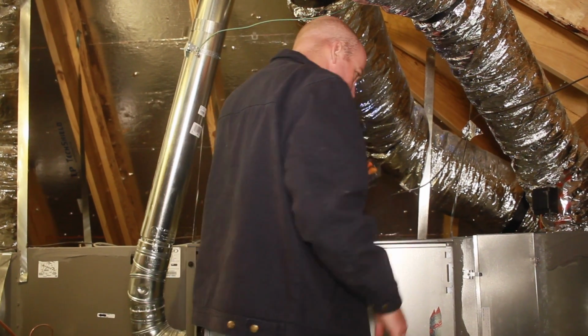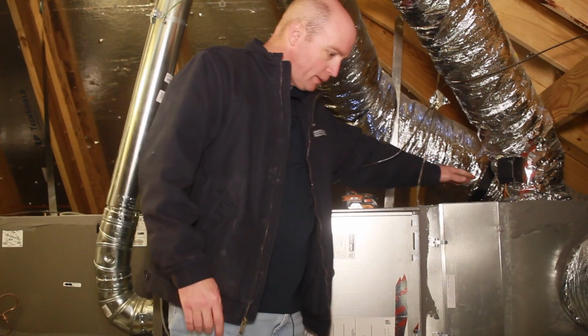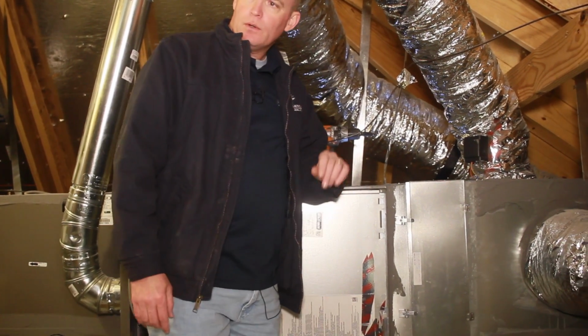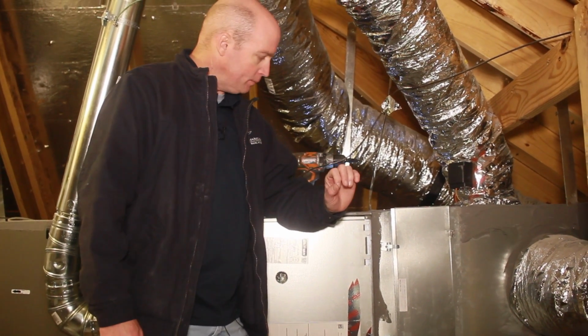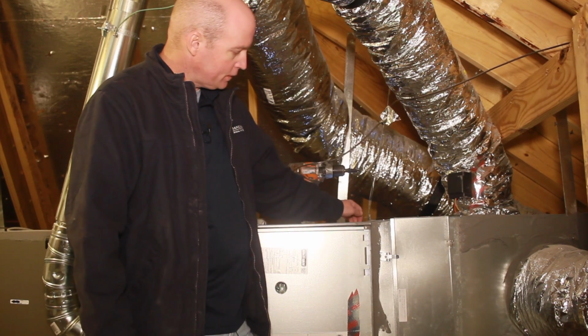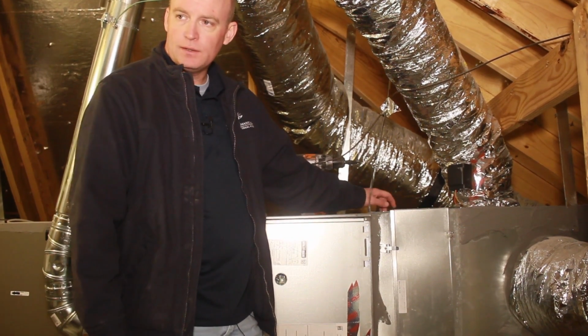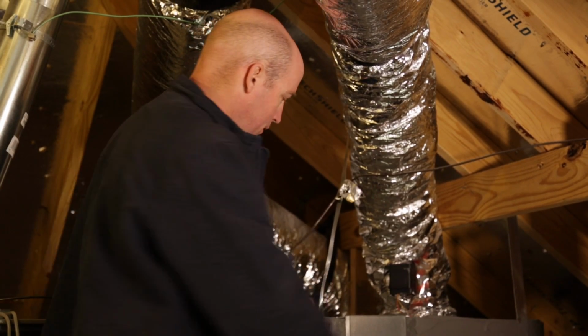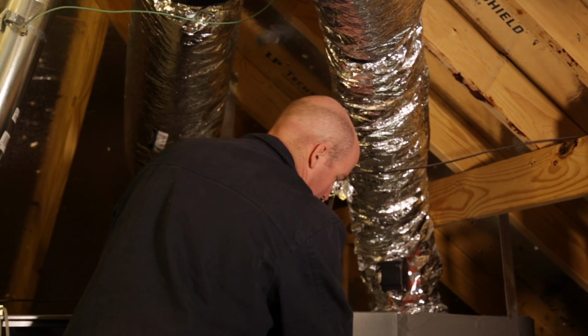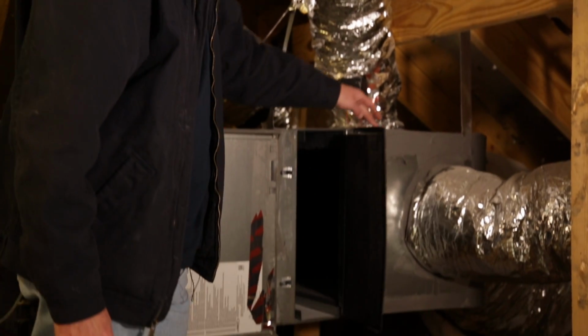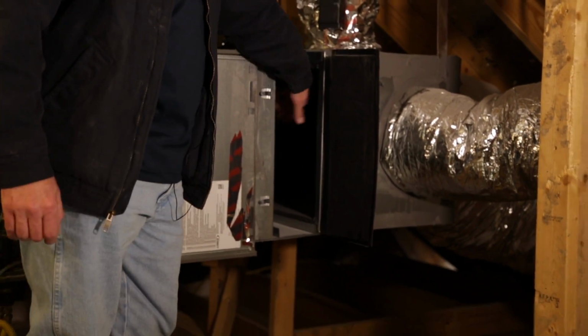The first hole we're going to put it in the return plenum. Now, earlier I said it has to be right at the back of the furnace or in the furnace after. The key thing is that it is after the filter. And what we'll do, I'll show you, we have our filter door open right now. There is no filter in here.